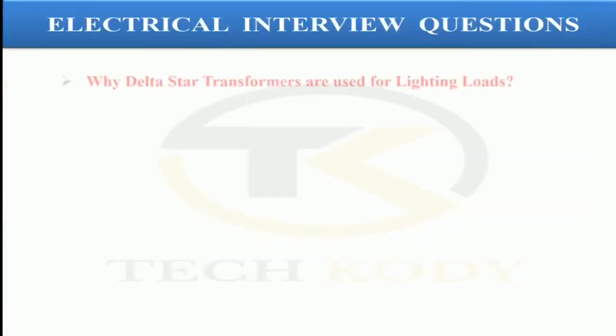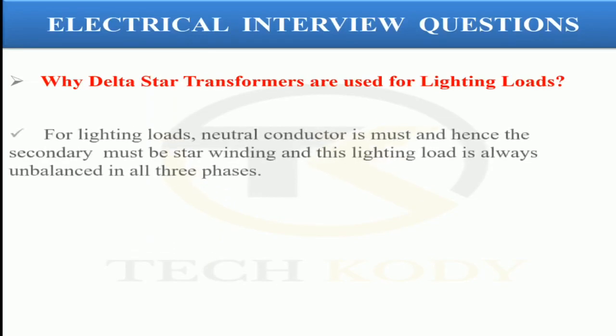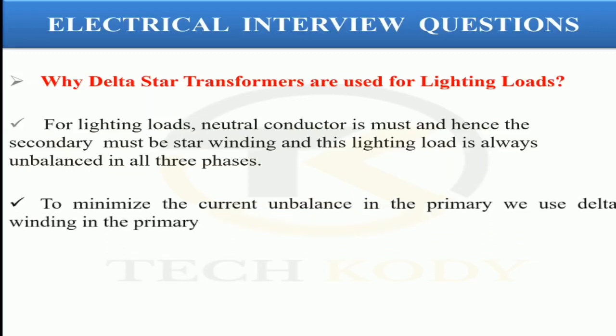The first question is: why are delta-star transformers used for lighting loads? For lighting, the neutral conductor is a must. Hence, the secondary must be star winding. This lighting load is always unbalanced across all three phases. To minimize the current imbalance in the primary, the primary must be in delta connection. So, delta-star transformers are used for lighting loads.